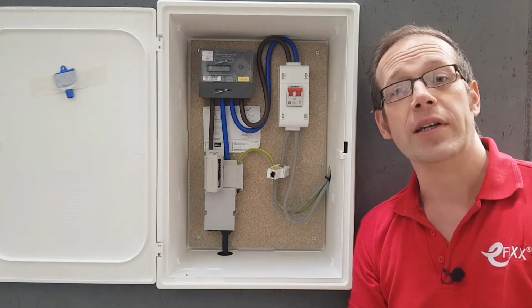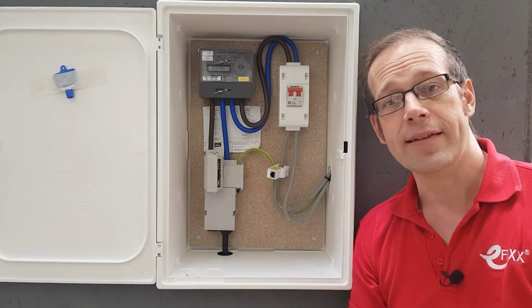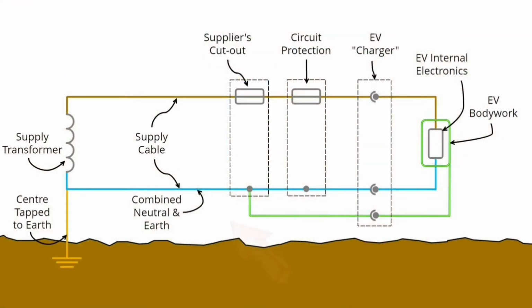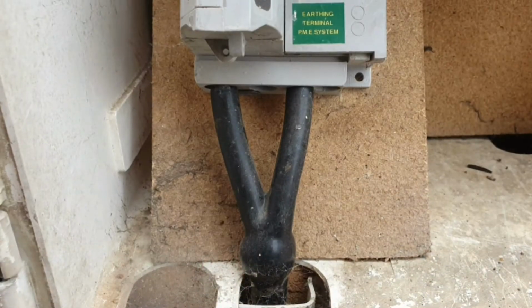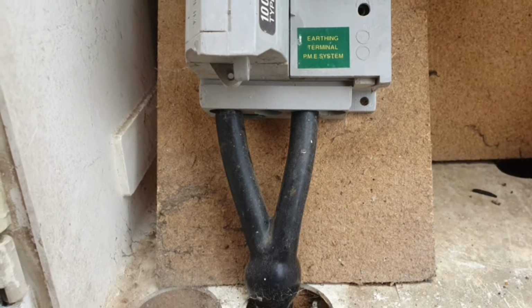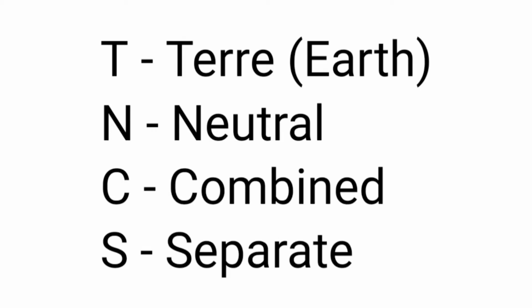Well, first of all, let's remind ourselves what a PME earthing arrangement is. In a TN-C-S system, the connection with earth is brought to a property by combining it with the neutral conductor. Once it reaches the building, the neutral and earth conductors are split and then remain separate within the electrical installation. And that's where we get TN-C-S from. Terra, or earth, and neutral, combined and then separate.